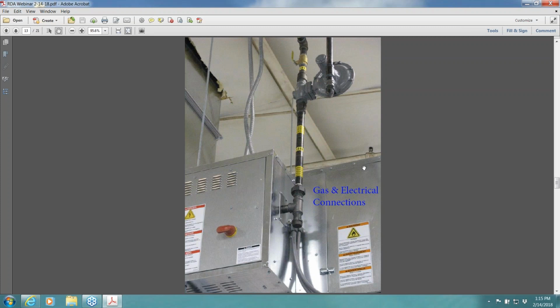On the gas line, you'll have a gas line that's supplied, and there's two big numbers. You need to know pressure and volume. For example, the unit we're looking at here is a 1.5 million BTU, and it requires 11 to 14 inches of water column. So BTU is your British thermal unit. That's the volume that you need. That's how much gas needs to be available. The pressure, 11 to 14 inches of water column, that's the amount of pressure that has to be on the line. You have to have both those numbers, and sometimes you will have more than that, and you get into this little gray circle up here. This is your regulator. The regulator brings the gas supply down so that you don't deliver too much to the air makeup system.